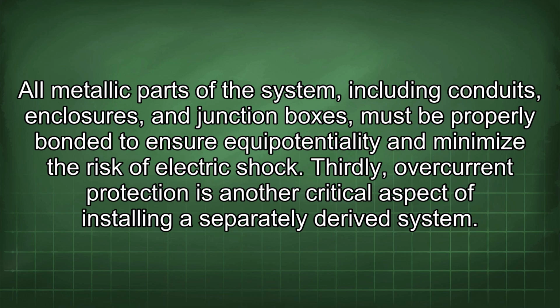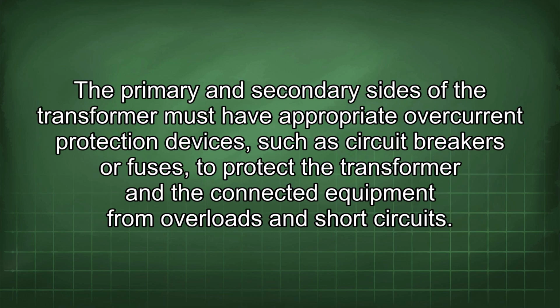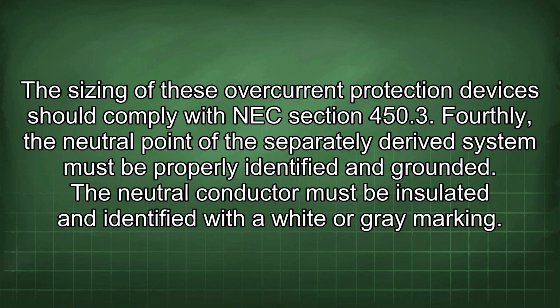Thirdly, overcurrent protection is another critical aspect of installing a separately derived system. The primary and secondary sides of the transformer must have appropriate overcurrent protection devices, such as circuit breakers or fuses, to protect the transformer and the connected equipment from overloads and short circuits. The sizing of these overcurrent protection devices should comply with NEC section 450.3.